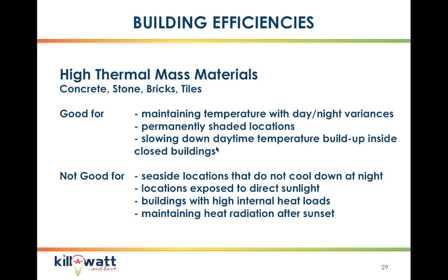It works well in shaded locations, slowing down the temperature build-up during the day inside a closed building, where warm air isn't allowed in. It's not good for seaside locations where there isn't much differential between day and nighttime temperatures, or locations exposed to direct sunlight, because direct sunlight will heat up that thermal mass very quickly.